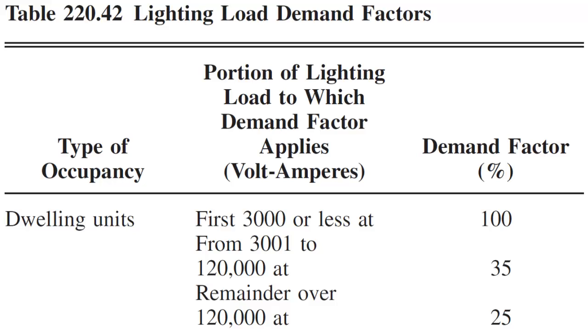Our lighting load demand factors are as follows. For the first 3,000 VA that we have, we have to take that at 100%. The rest, we take at 35%. The reason I say the rest is because you will probably never come up with a calculation that would be higher than 120,000 VA.